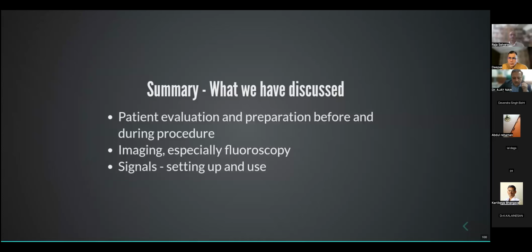Yeah, so what I found in my experience, whenever this has happened, the ground patch on the patient either had too much gel applied, which was overflowing, or too little gel applied. The other issue is, whenever the ablation catheter is used for pacing, if you have chosen the ablation distal for pacing, and you start ablating and you forget that you've chosen it for pacing, that noise can come in sometimes. Yeah. So that can be checked.